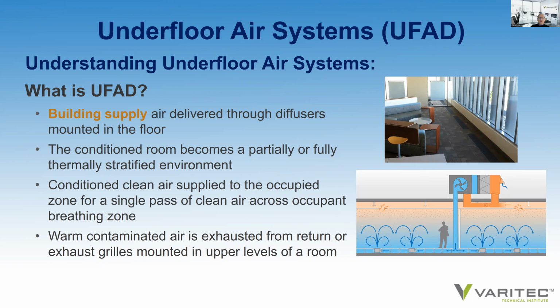So what is UFAD? What is an underfloor air system? It is a system whereby building supply air is delivered through diffusers mounted in the floor. The conditioned room becomes a partially or fully thermally stratified environment. If you recall from previous sessions on thermally stratified environments, the actual airflow mechanics involved in these systems and how they differ from a mixed air system. Conditioned clean air is supplied to the occupied zone, and a single pass of clean air across the occupant breathing zone occurs. And consequently, warm contaminated air is exhausted from return or exhaust grills mounted in upper levels of a room.